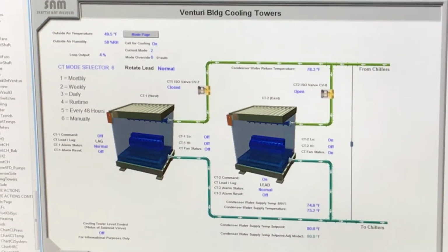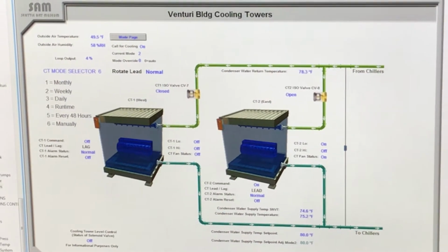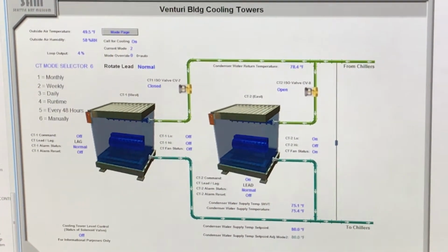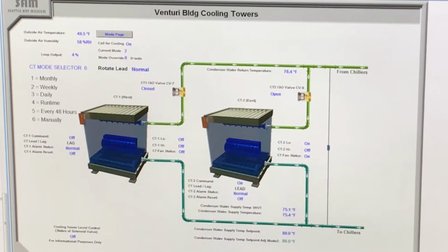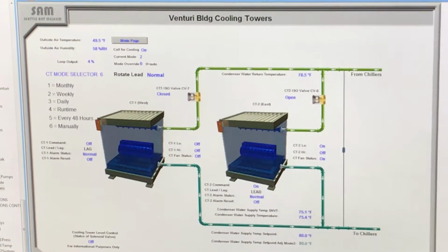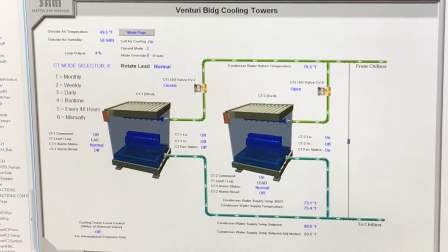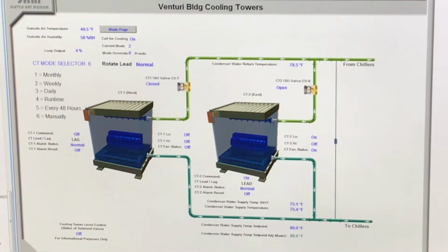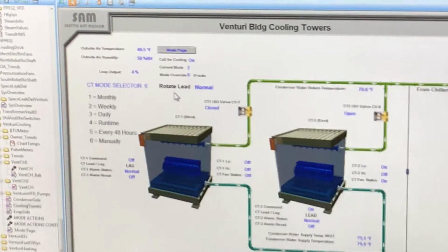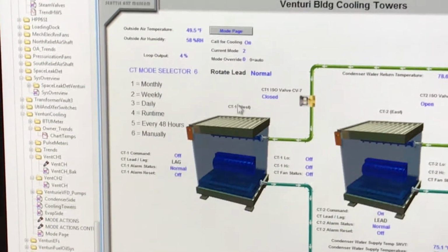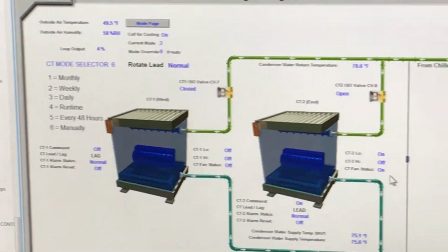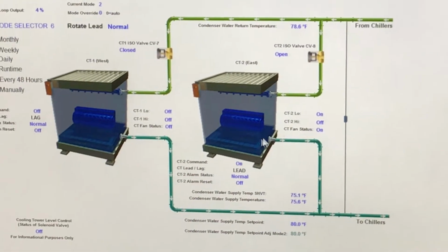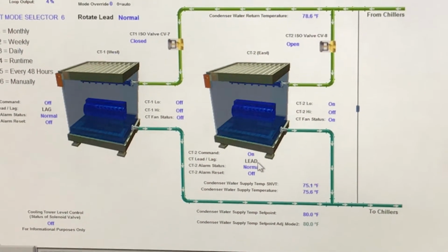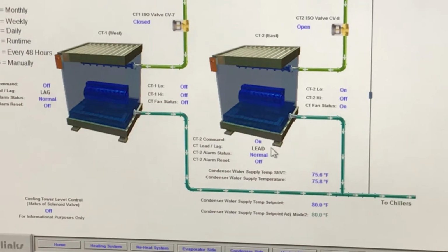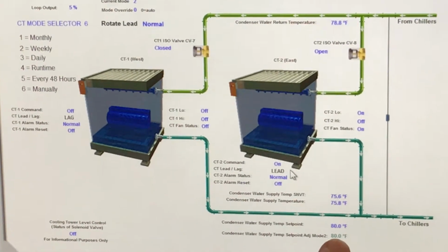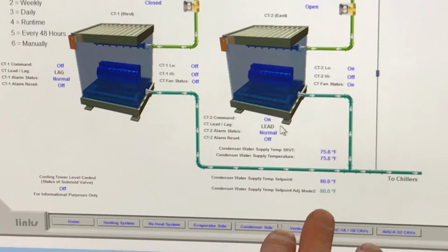So, cooling towers, we have a couple of new things here. Basically, it's still on the lead-lag situation, where it starts off with one chiller as lead, and that is right now Number 2. That will tell you here, lag, lead. It'll start there and try to maintain the set point down here, which changes depending on what mode you're in.